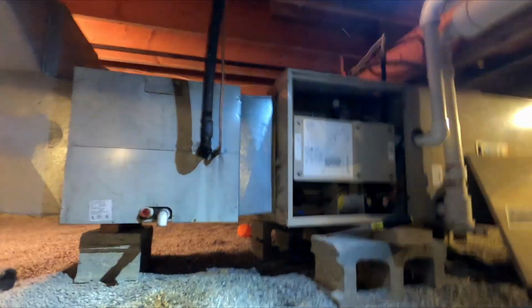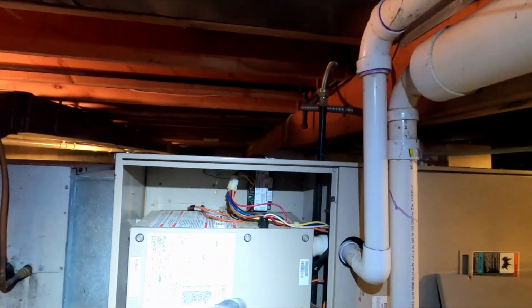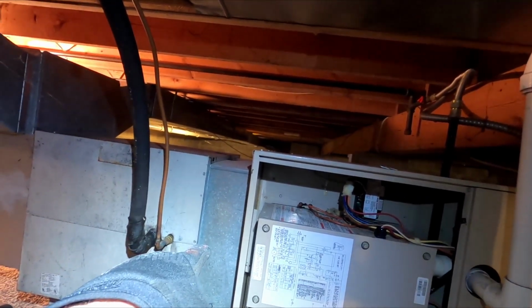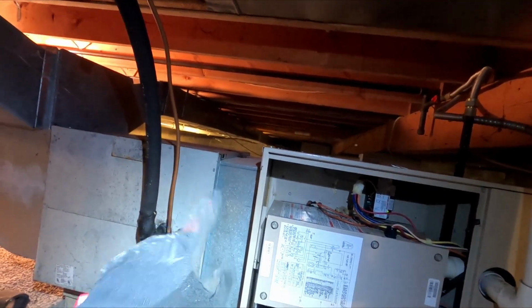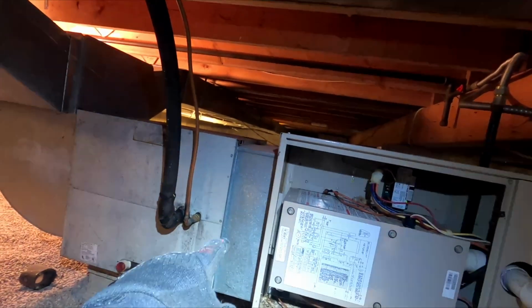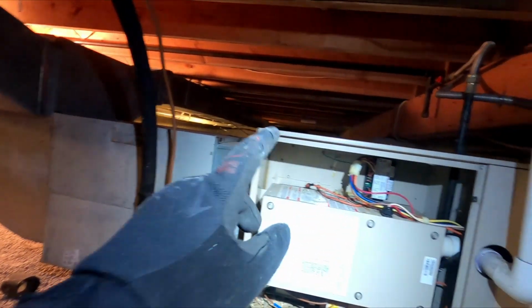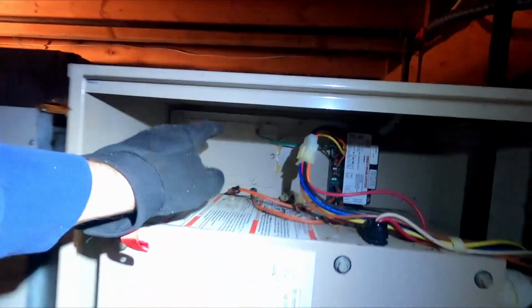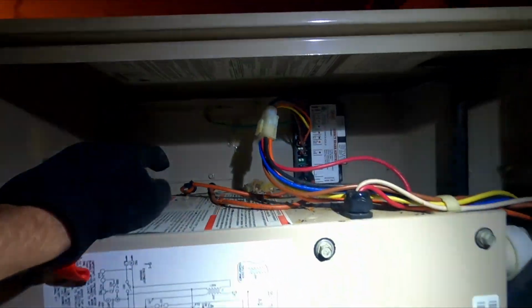Okay, the board's been replaced. But what I'm saying is, positive pressure heat exchanger, before the thing starts up, stick your CO meter in there and check for CO before the fan starts. Also, here's an inspection port.